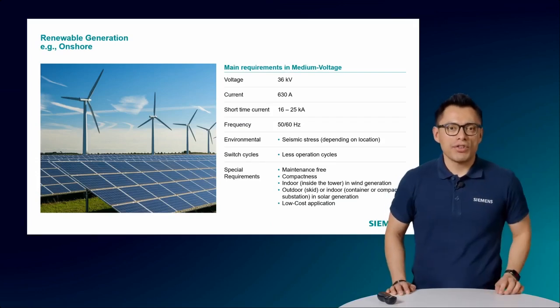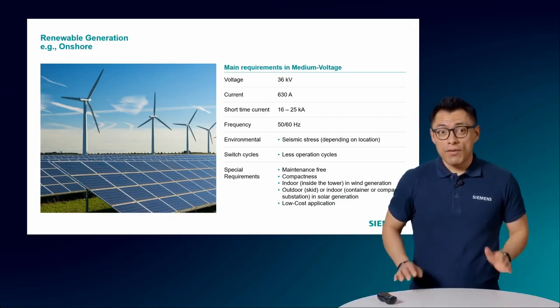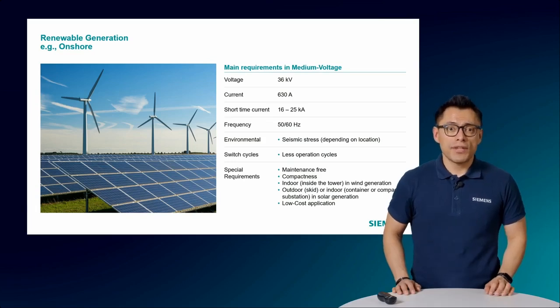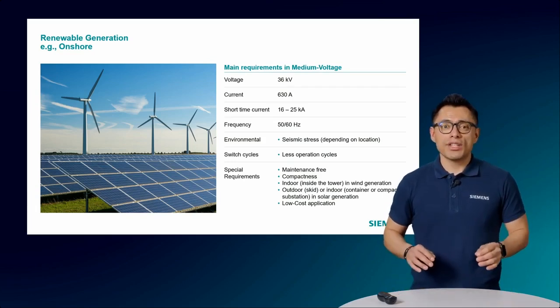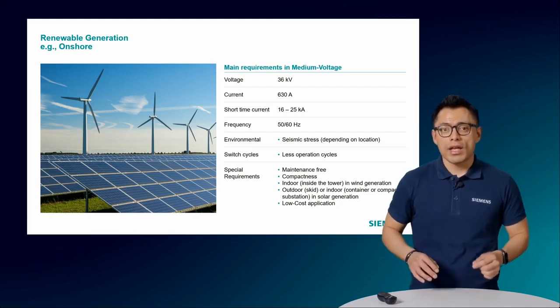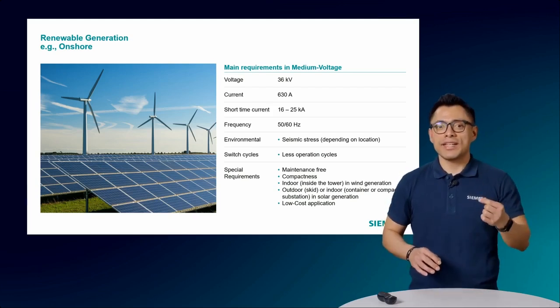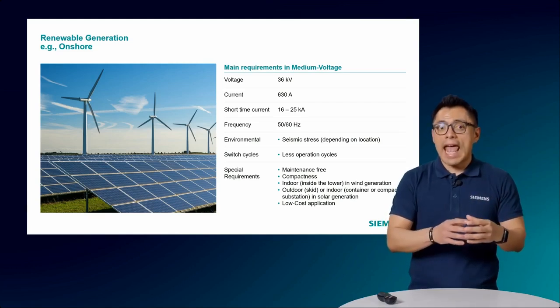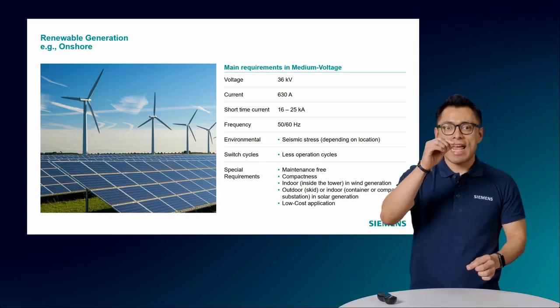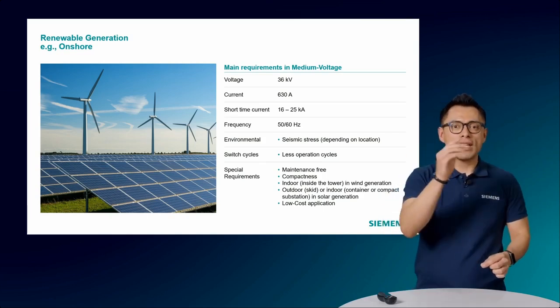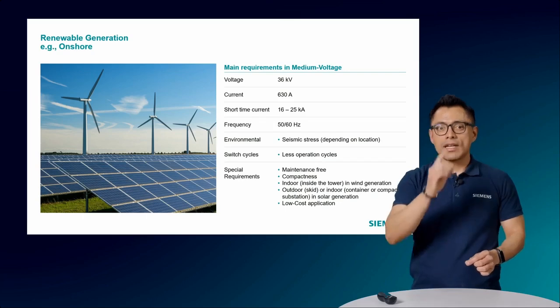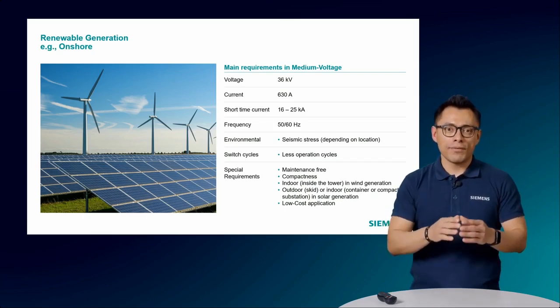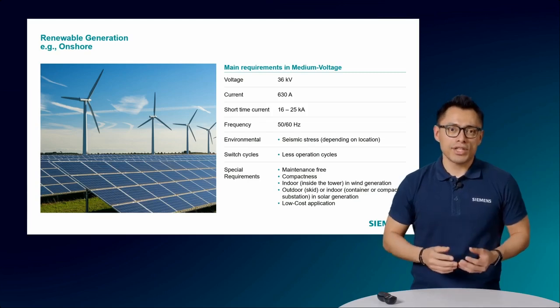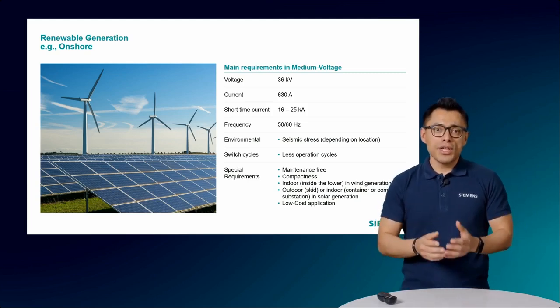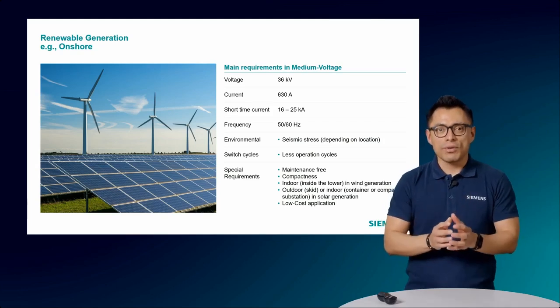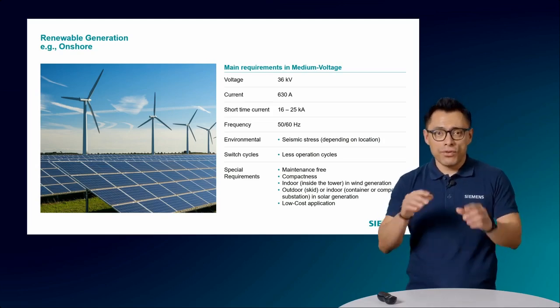Onshore wind power generation is another very interesting application. For that, the switchgear needs very special features. For example, they need to withstand vibration stress and harsh environmental conditions. Due to the fact that the switchgear is installed inside the wind turbine, and due to the height of the wind turbine and the strong wind, they tend to swing around 1 meter on the top. This causes some vibration at the bottom of the tower, where many times the medium voltage switchgear are installed. Switchgear also needs to have a compact design which makes them ideal for being introduced through the narrow door of the tower.